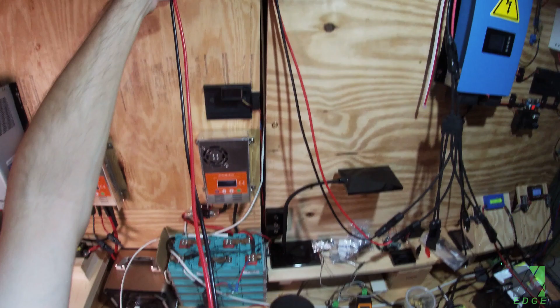Alright, this is positive. Now I need to verify the polarity of this charge controller before I hook these cables up, because MC4s are tricky—they can be the wrong way around. I got to make sure of that before I hook them up. Alright, the polarity has been verified. These cables are not live, so it's okay to plug them in. MC4s, you really shouldn't plug them in when they're live.